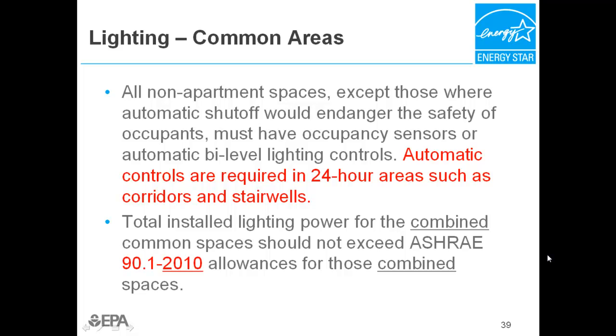They are, however, required in spaces intended for 24-hour operation, such as corridors and stairwells. Generally, if emergency lighting is required by local code to remain on for 24 hours, this requirement can still be met by using sensors on the fixtures not designated as emergency.